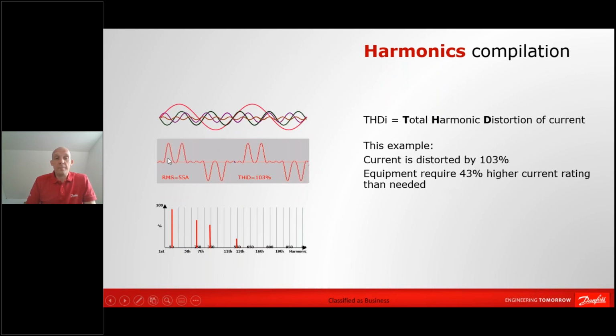So now I'll stop here. You can see here the RMS current went up. So the current that the frequency converter is consuming, the green curve you saw to begin with, is actually pulling 55 amps from the power supply. We are only using the 39 amps for generating torque to the motor, whereas the 55 is actually what we are pulling from the power supply. That basically means that the power utility has to deliver more current than what we are consuming in the frequency converter for generating torque to the motor. So you can say we are drawing an disproportionate amount of current from the power supply, simply because of the way we are pulling the current from the supply grid.